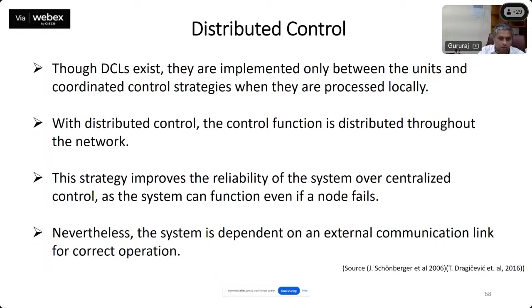The challenge with the decentralized control scheme is you really don't know what is happening on the other side of the network, because you're just worried about controlling your own local parameters. In the centralized controller, you're always busy taking care of the entire global system, so the advantage is you get to know in detail about everything happening in the system. But the challenge could be communication delays, attacks, and cyber threats, man in the middle attacks, false data injections, and because of this there could be a lack of security and stability in the system. In distributed control, you inherit the advantages of both the decentralized and the centralized control.